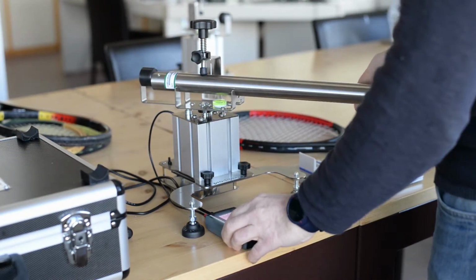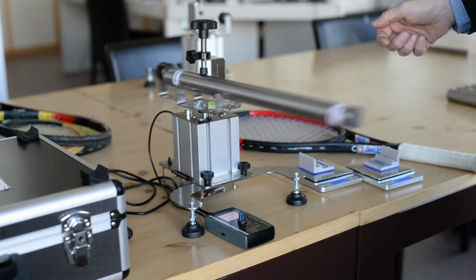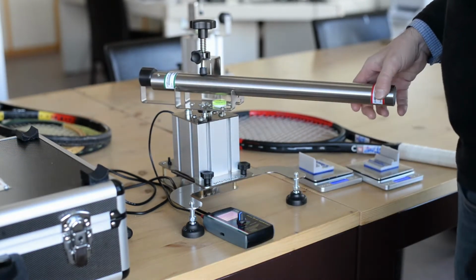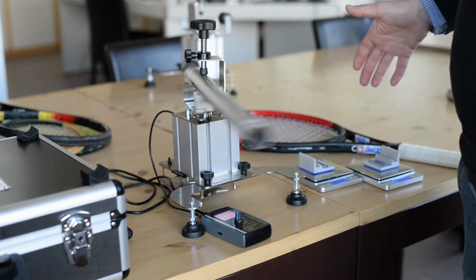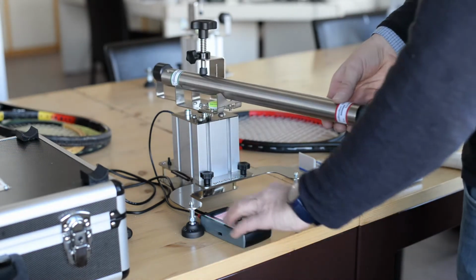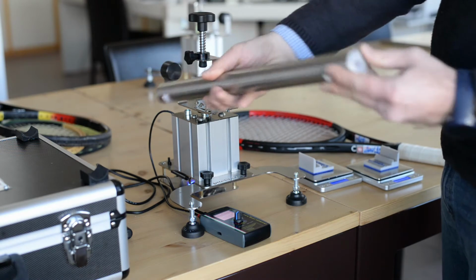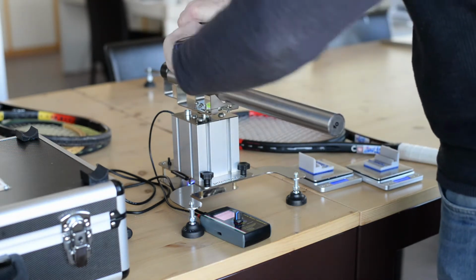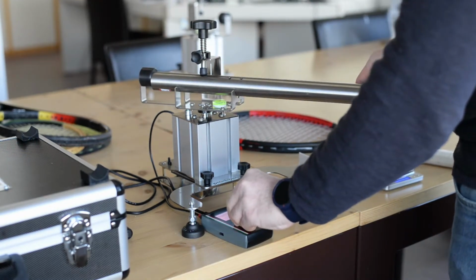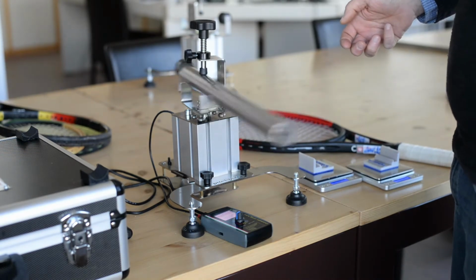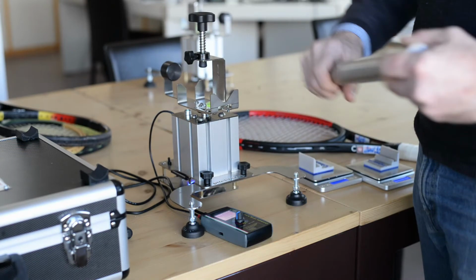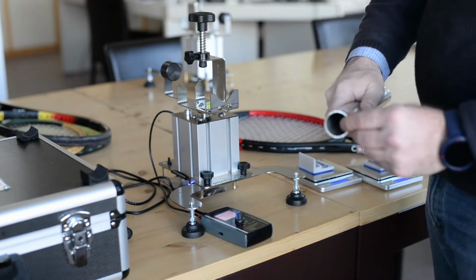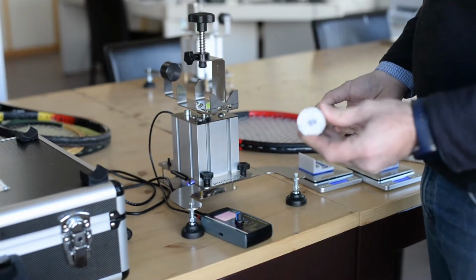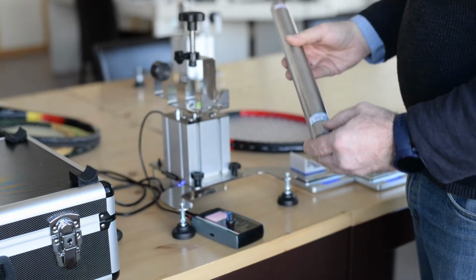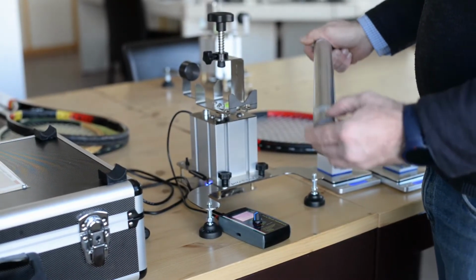Pressing the central button and letting the bar roll, I get the first calibration time, and then using the same rod I can fix the second time. We decided to use a single bar with two faces, open on one side and closed on the other, so we can use a single bar having two calibration points to give you the best results in terms of precision during calibration.